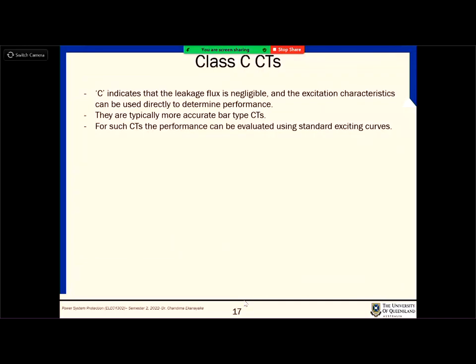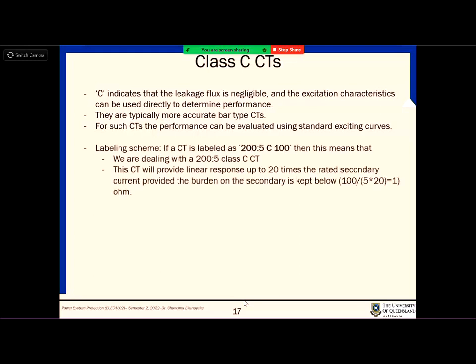Class C is easier to analyze because it indicates that leakage flux is negligible. The C has little leakage flux, so the excitation characteristics can be used directly to determine the performance. These excitation characteristics are provided by the supplier, so you have standard C-type curves. Usually they are more accurate, and therefore their performance can be evaluated using the standard excitation curves, which I will show you in the next slide.